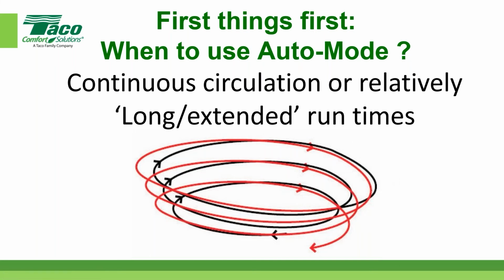And that's typical, right? So as long as these things are working in a way that's going to give you long run times, I believe Tecmar is a good example of some of the control strategy that they use. They use zone synchronization and zone staggering, and they try to keep the zone that has the greatest demand running on almost a continuous basis. Now, the other example I was referring to earlier is that if the only thing that turns the pump off is a warm weather shutdown condition, then you've got to know that pump's running continuously.